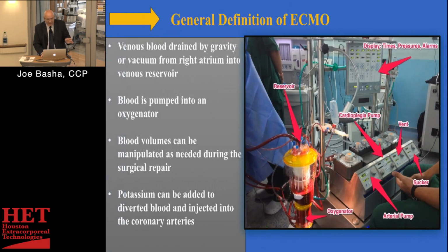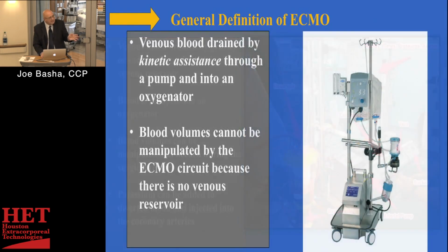So contrasting that, what you see here, to this, you can see that it's got a lot of similarities in necessarily what it does, but it's very different. Venous blood is drained by kinetic assist, so when the centrifugal pump is spinning, it's pulling the blood out of the patient, and then it goes from there into the oxygenator, and that one outlet continues to flow up to the return, wherever that return may be, and we'll talk about all those cannulations. But the major difference is that you can't modify the volume of the patient because it's a closed system, so you don't have that reservoir anymore.